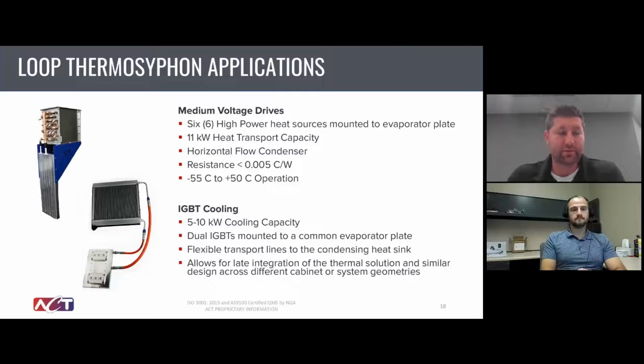And then looking at some examples here, the top one there is a medium voltage drive cabinet. So this had kind of the example I was alluding to, multiple high powered sources on that single evaporator plate. So the metallic kind of silver aluminum plate that you see there coming vertically had 6 heat sources mounted to it, so 3 on one side, 3 on the opposite side. It used refrigerant as the working fluid, and again, transferred that heat in kind of the schematic you saw on the previous slide to an air-cooled condenser. And this one had a fan coupled with it and utilized that heat sink that you can see there with some horizontal airflow.